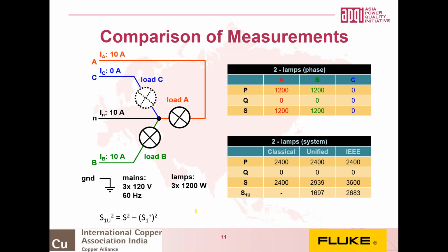So IEEE 1459 introduces the effective power. That's actually SE. It's mathematically sound and complete, but it's hard to read for a non-mathematician, and some of the parameters associated with the effective power are difficult to link with real physical phenomena. So it multiplies the neutral current by all the phases and phase-to-phase voltages, which results in a heavy influence of the neutral current on effective apparent power and effective fundamental apparent power. For that reason, it gives a high value of apparent power, and the high value in this case is 2,683 VA for the unbalanced power in this example.